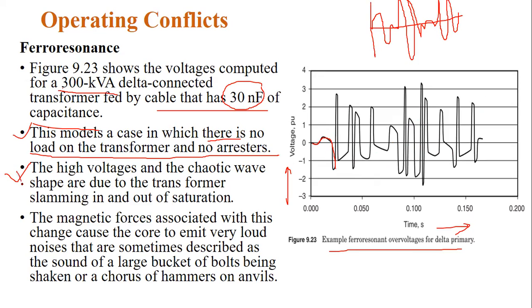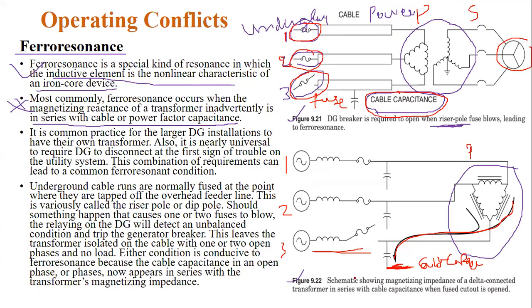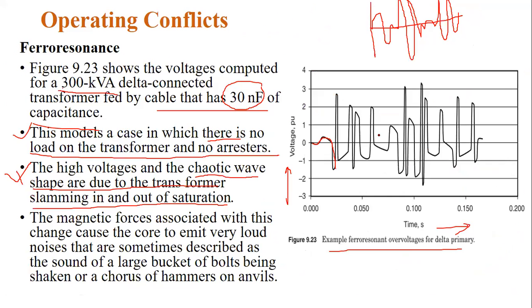Now see this. You can see this condition. The high voltage and this wave shape are due to the transformer slamming in and out of saturation. So when the fuse is blown, and the on and off cases of the circuit breakers, these fuse-blown cases lead to this. What will happen when one of the phases is open? The cable capacitance will supply some power. So once the open case and the capacitor on case occur, it leads to some problem.